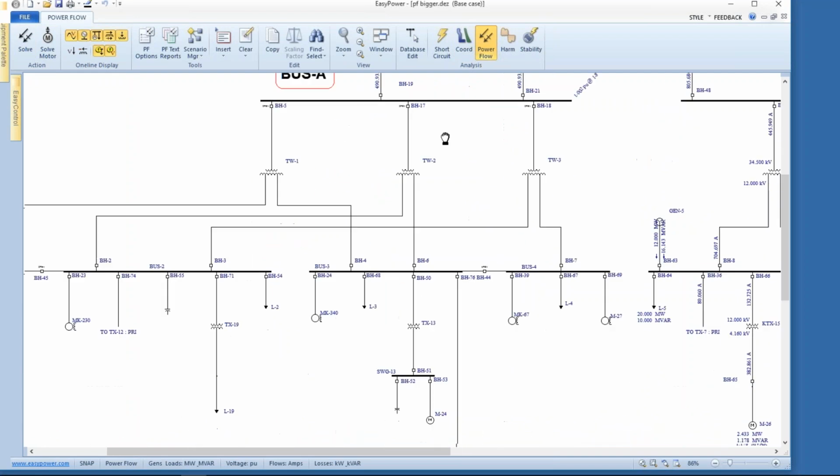Well, if I come down here now and look at what's going on, these are all interconnected. I have 3 winding transformers supplying a series of downstream buses, and they're all potentially interconnected, and so consequently this is a fairly complex system.